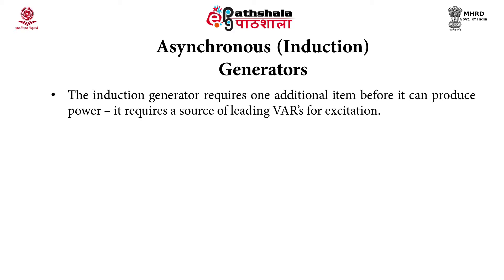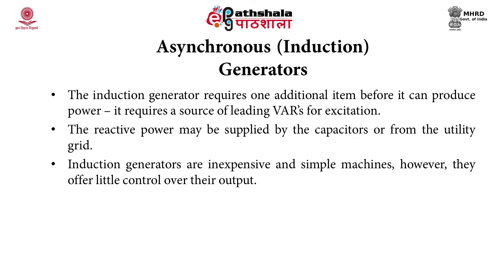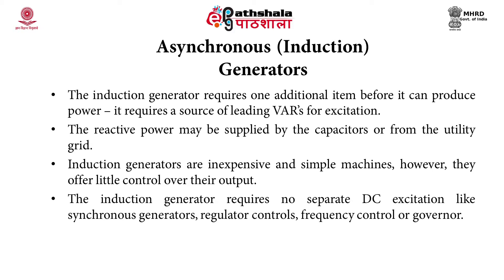The induction generator requires one additional item before it can produce power — reactive power, which may be supplied by capacitors or from the utility grid. Induction generators are inexpensive and simple machines. However, they offer little control over their output, and the induction generator requires no separate DC excitation like the synchronous generator.